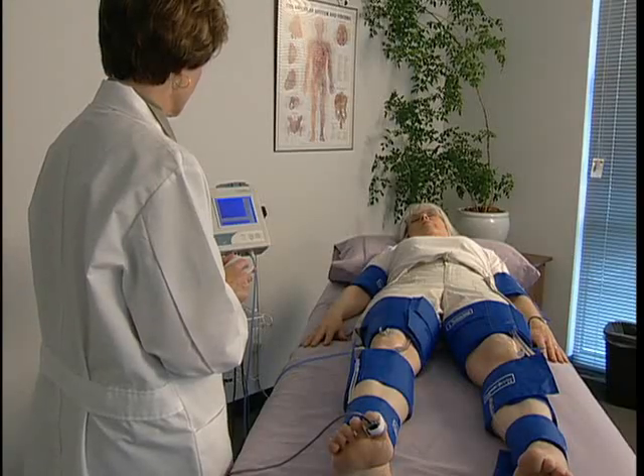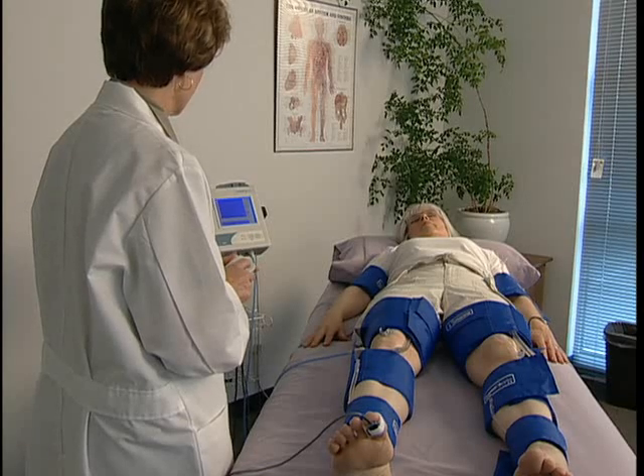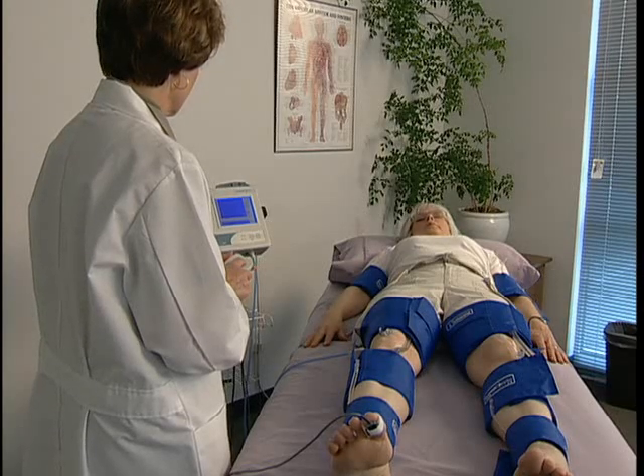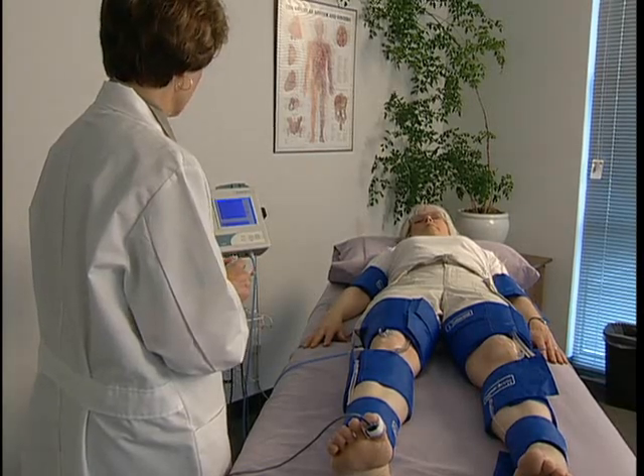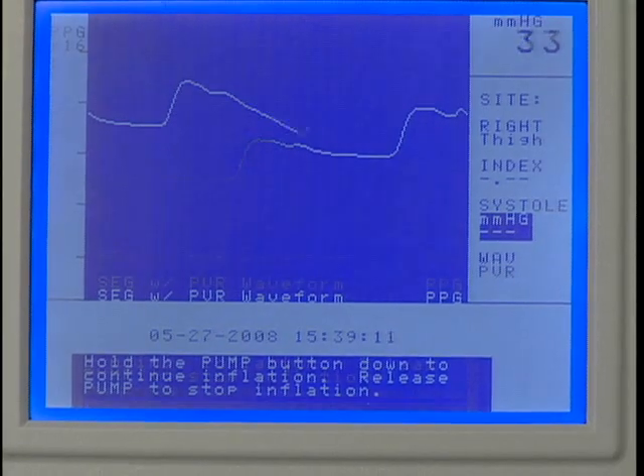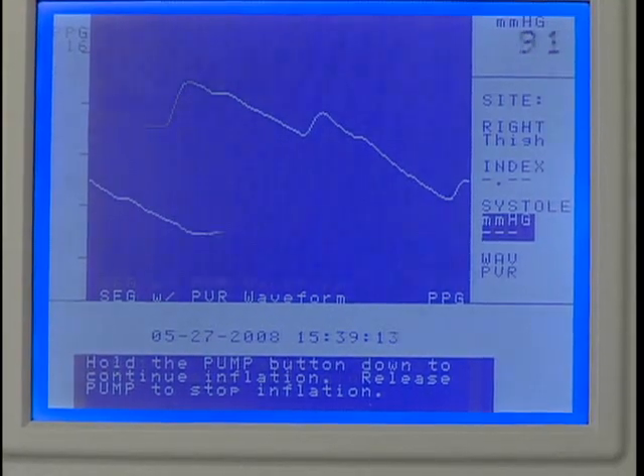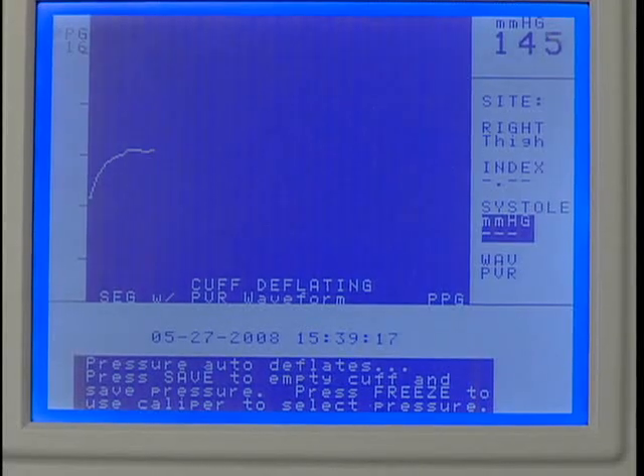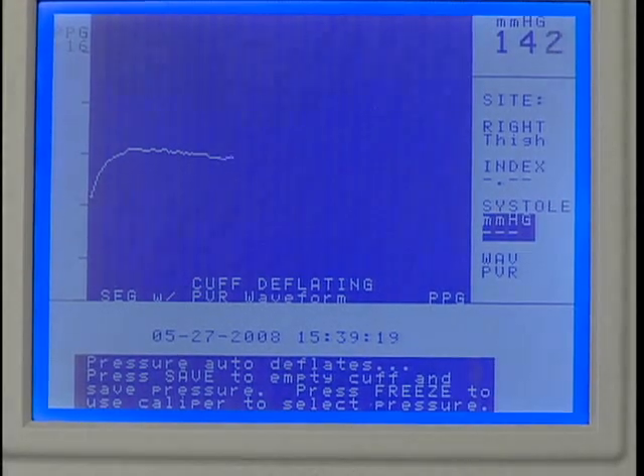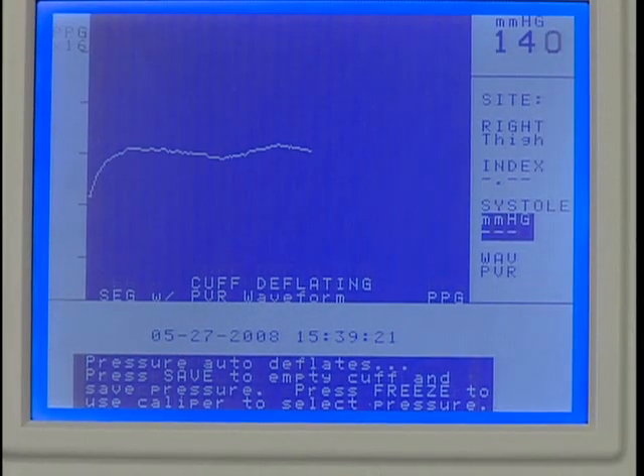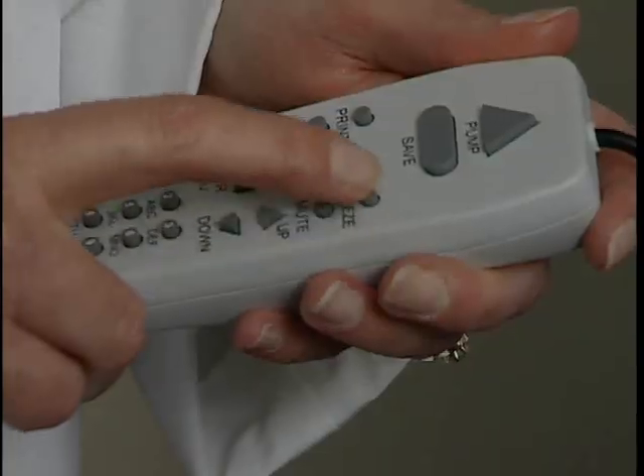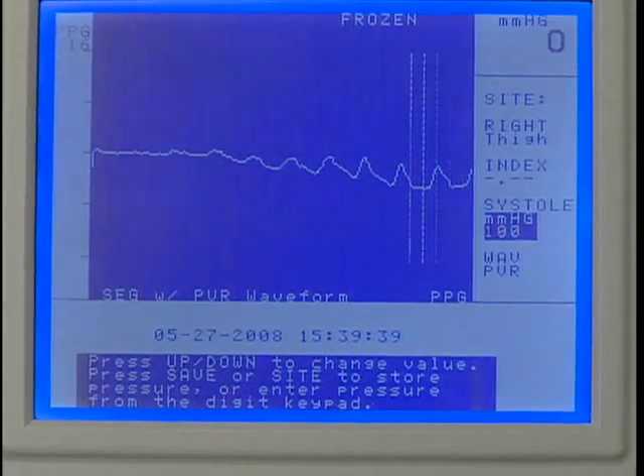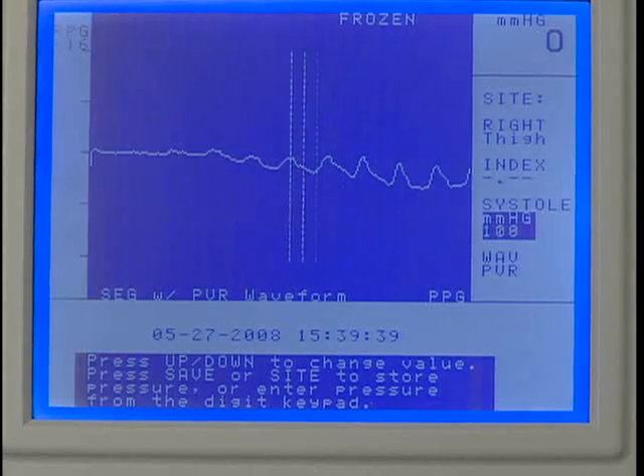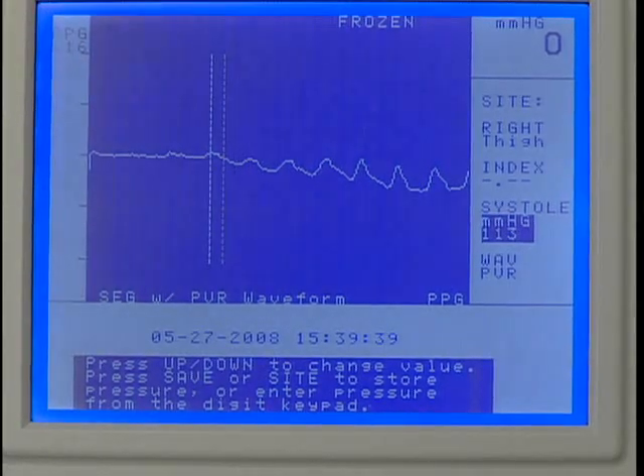Now we'll obtain the pressure using the PPG probe. Once a stable waveform is obtained, press Pump to inflate the cuff to a pressure approximately 20 millimeters of mercury above the pressure where the PPG pulsations disappear. The cuff will begin to deflate automatically once the pump stops. After several pulses reappear, press Freeze and use the up or down key to move the caliper to the first upward slope. Press Save to record the systolic pressure.